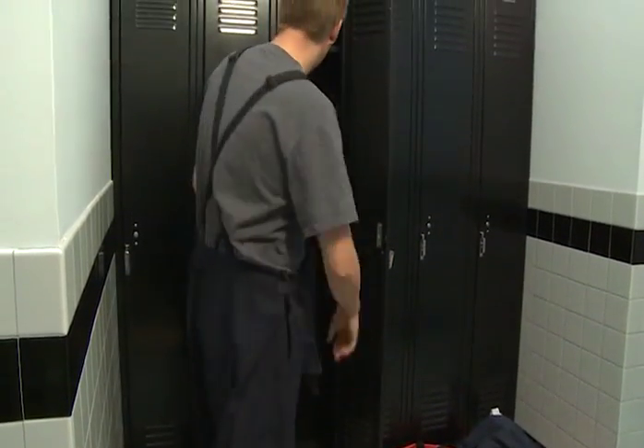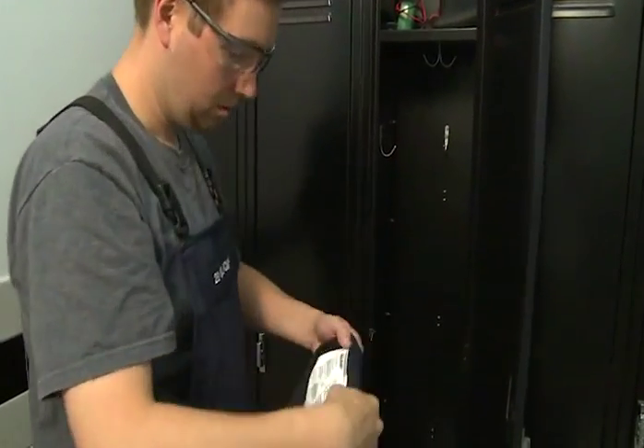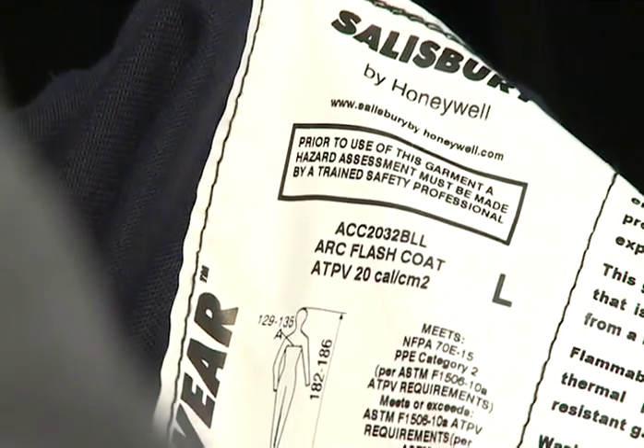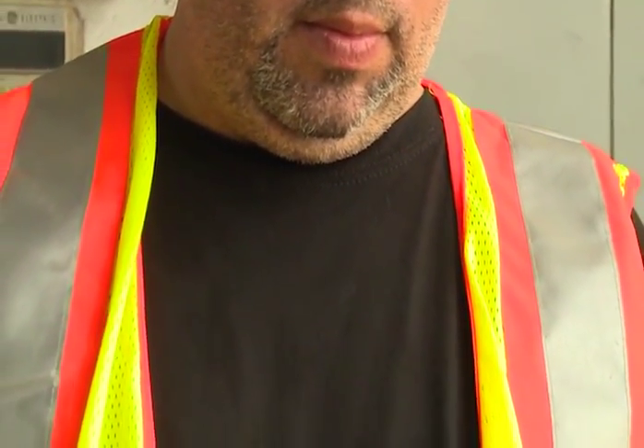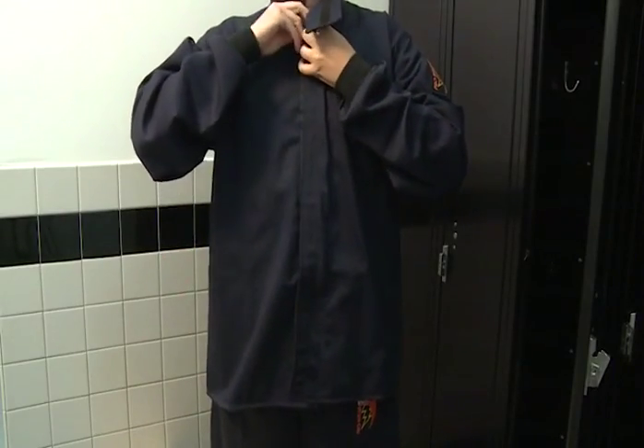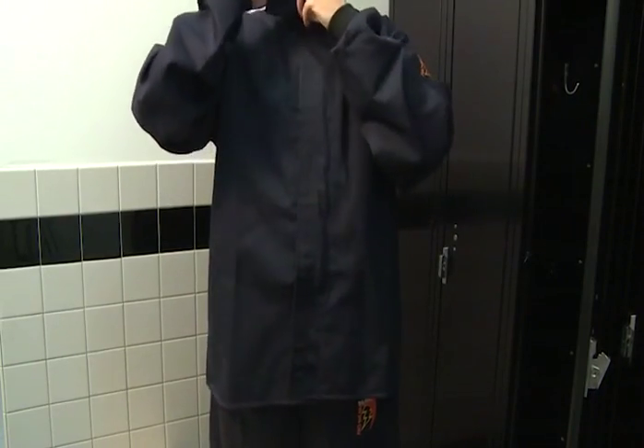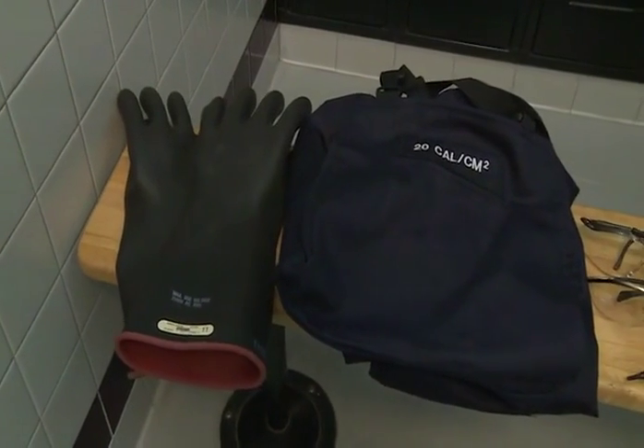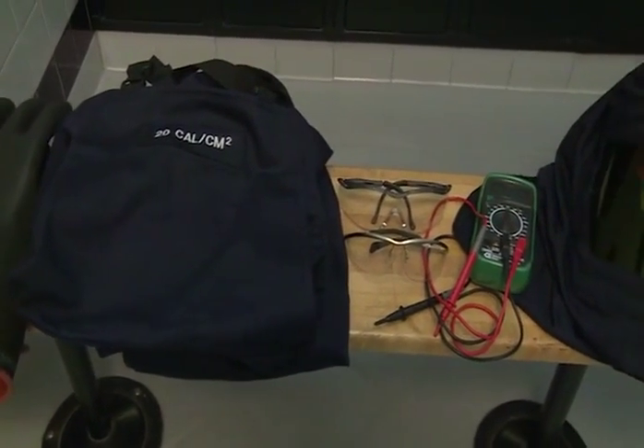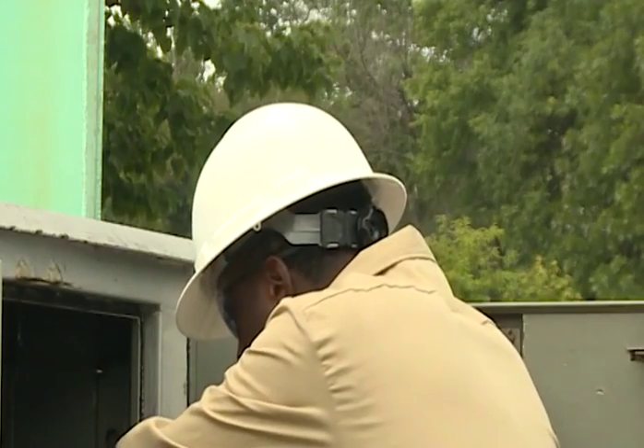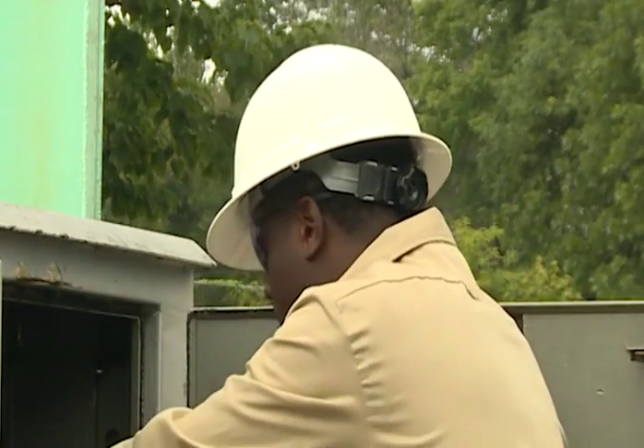This is why electrical workers always put on arc-rated protective clothing when they approach a potential arc flash source. The arc rating describes how much heat the clothing can resist without damage. To calculate the arc rating you need for a particular task, you determine how many units of heat you would receive where you are working if an arc flash occurred in that equipment. You then can choose clothing with an arc rating that meets or exceeds the protection level for that amount of heat. Other arc-rated PPE, such as gloves, safety glasses, or face shields, is selected in the same way. But the heat energy generated by an arc flash is not the only hazard. There is also the arc blast to consider.